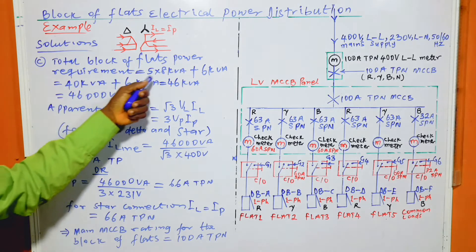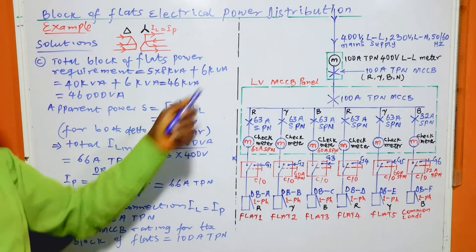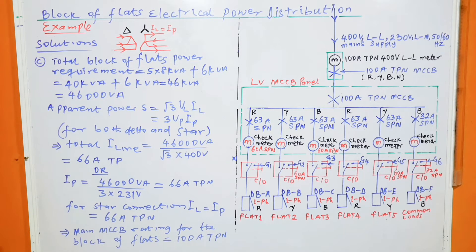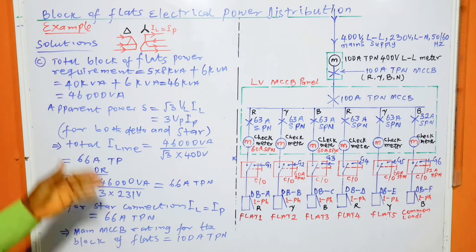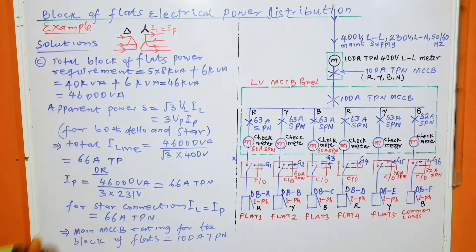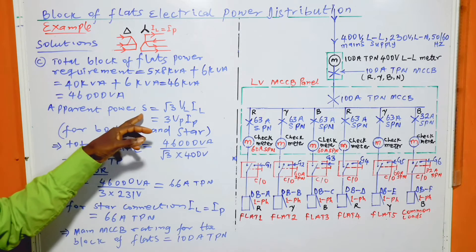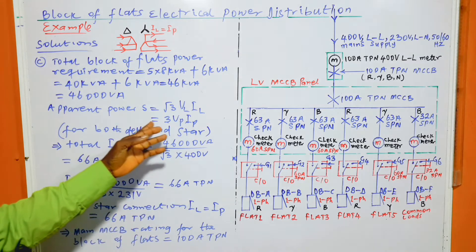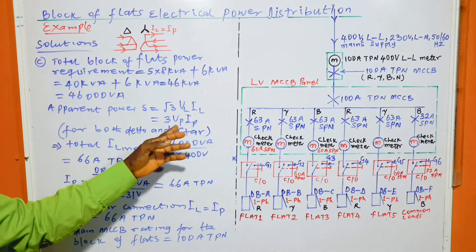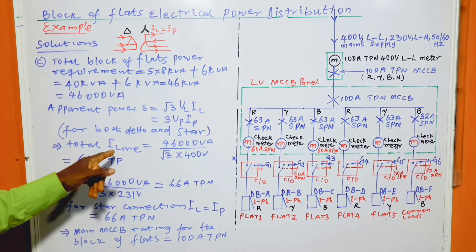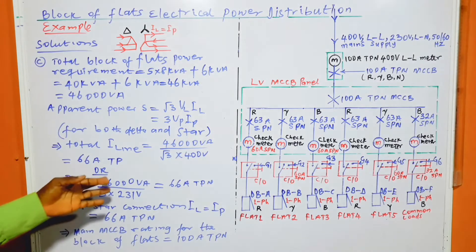Part C: total block of flats power requirement equals 5 times 8 kVA plus 6 kVA — five identical flats each requiring 8 kVA plus the 6 kVA common load — giving 46 kVA, which equals 46,000 VA. From apparent power S = √3 × V_line × I_line, which also equals 3 × V_phase × I_phase for both star and delta, we calculate the line current to be 66 amperes, three-phase.